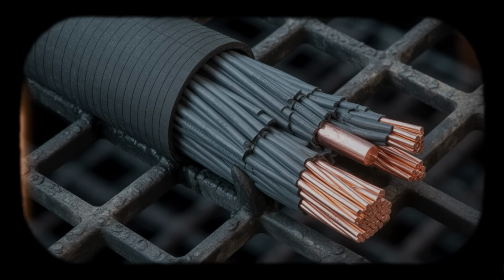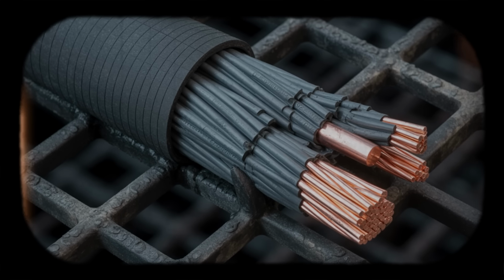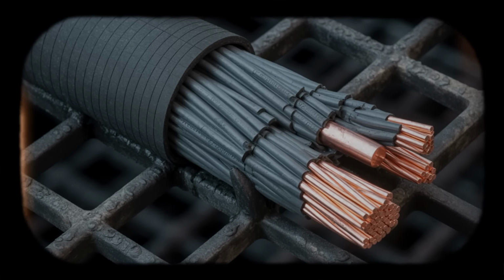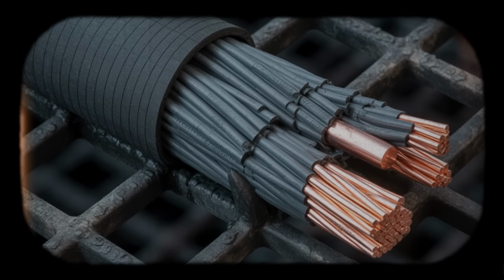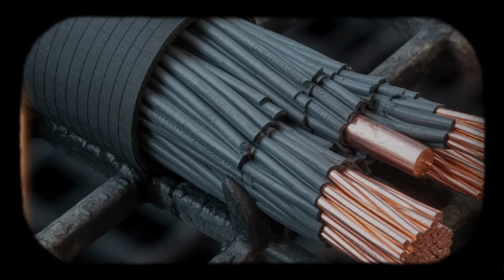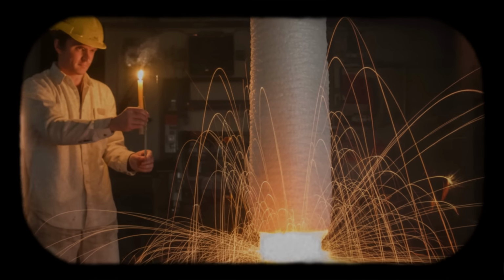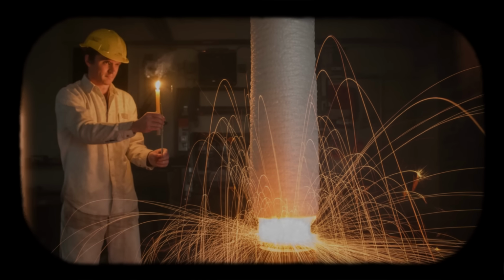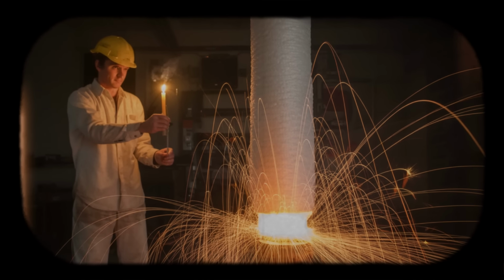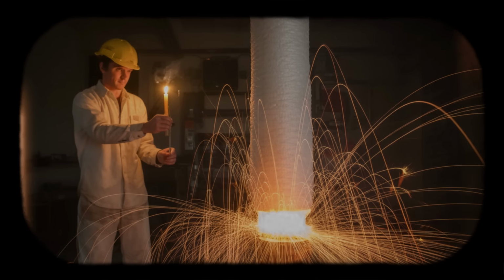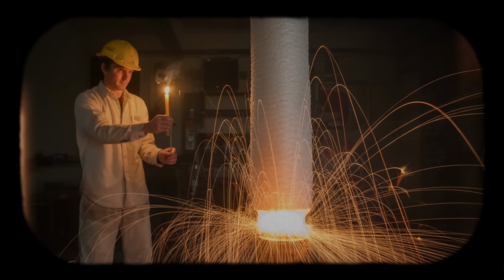The situation approaches a threshold. If fire spreads to several additional cable trays, shutdown cooling capability could become unrecoverable. The reactors would still be shut down. Control rods are inserted by mechanical springs, not by electrical signals. But removing decay heat would require improvised methods without reliable instrumentation to guide operations.